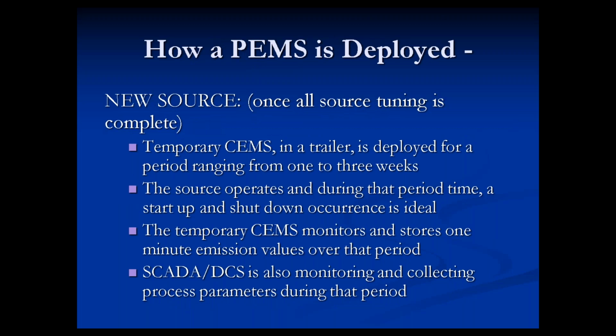So getting into the nuts and bolts of how a PEMS is deployed, basically when a new source is on site, it's important that it be fully commissioned, lined out, and tuned before we do our work relative to the deployment of the PEMS. So once it is all tuned, we'll go ahead and deploy a temporary CEMS in a trailer, much like you'd see in a stack test trailer. And we deploy that for a period of time ranging from a week up to 3 weeks or so. And during that period of time, we're monitoring the emissions of NOx, CO, O2, etc.